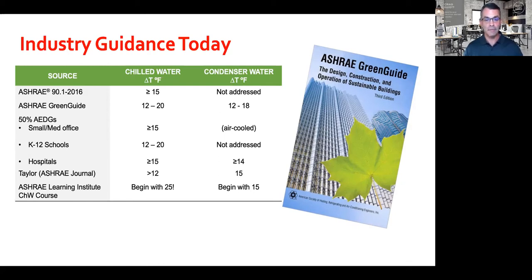Clearly, the industry recommends that systems be designed with significantly higher delta Ts and lower flow rates than in the past, but we will address designing a system to get the most BTUs out of your plant with the least amount of energy and cost. Next slide, please.